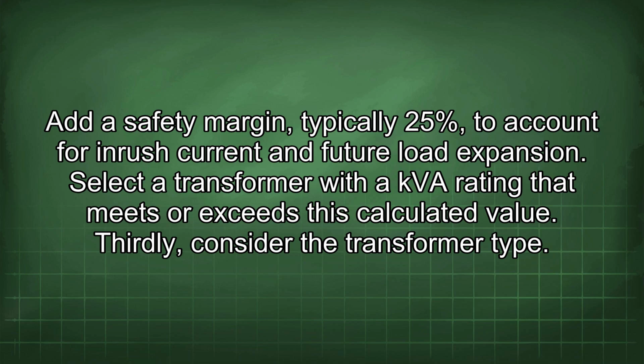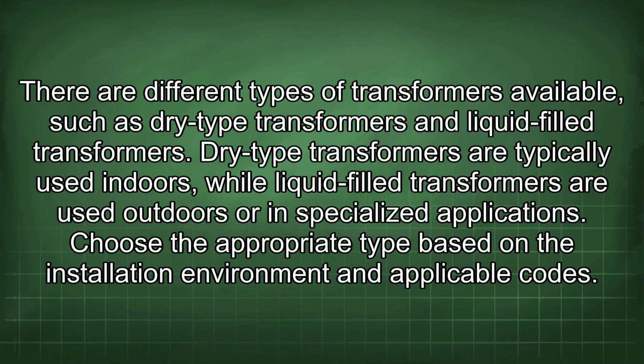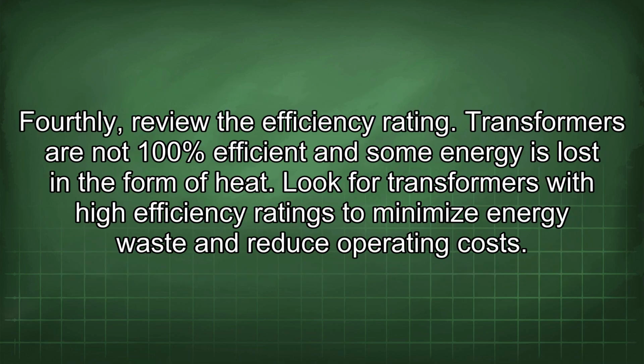Thirdly, consider the transformer type. There are different types of transformers available, such as dry-type transformers and liquid-filled transformers. Dry-type transformers are typically used indoors, while liquid-filled transformers are used outdoors or in specialized applications. Choose the appropriate type based on the installation environment and applicable codes. Fourthly, review the efficiency rating.